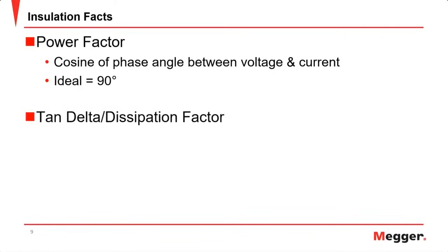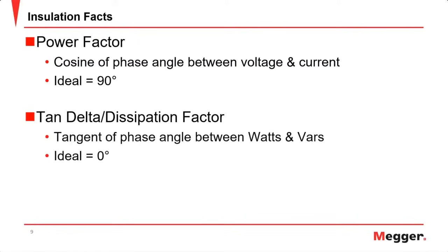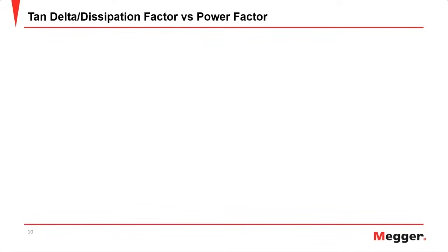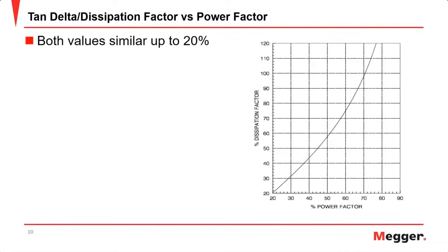But sometimes you might hear the term tan delta or dissipation factor used when talking about power factor testing. It's the same exact measurement method, but we're looking at a couple different parameters. So for tan delta and dissipation factor, we are looking at the tangent of the phase angle between the watts and the vars. And here, ideally, that phase angle should be 0. And what's important to note about tangent delta or dissipation factor versus power factor is that up to 20%, they are exactly the same. And after 20%, they start to diverge.